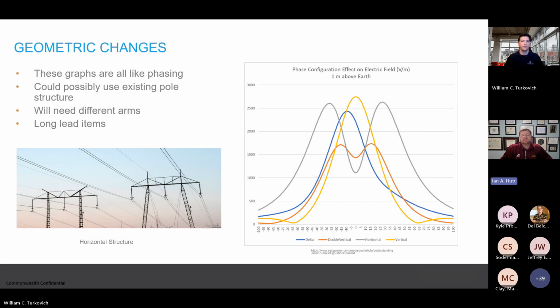What we can find too is when we go to a double vertical, and you have the two circuits phased opposite, so CBA top to bottom, and then ABC top to bottom, we tend to get a lot of cancellation. That's really nice. It knocks that top peak down considerably on your magnetic field and electric field levels, but it pushes that electric field out towards the edge of the right of way. You can see that with the orange camel hump drawing there in the middle.